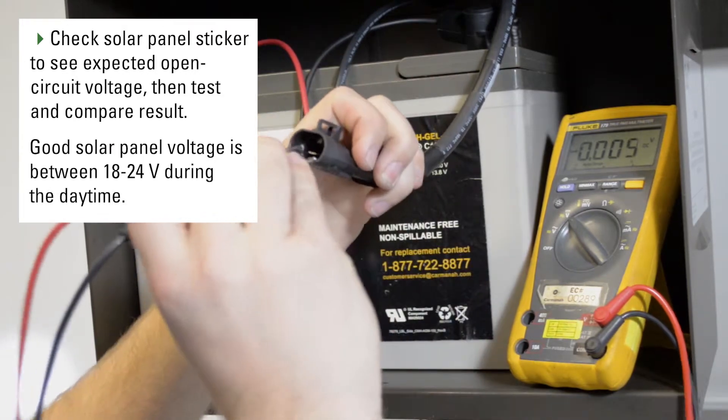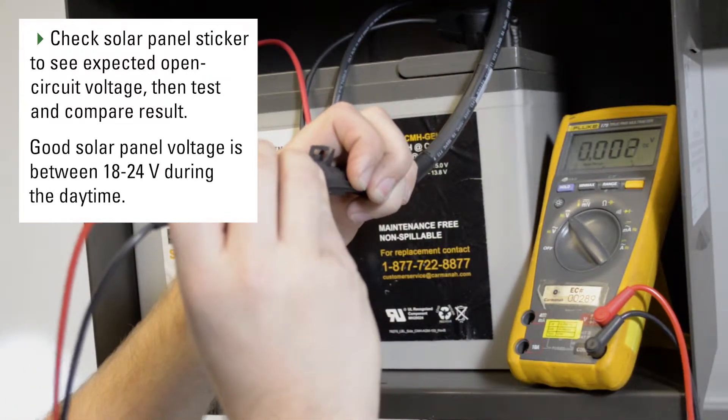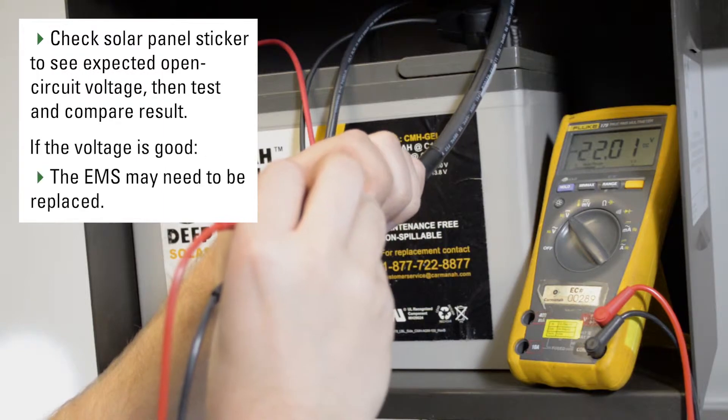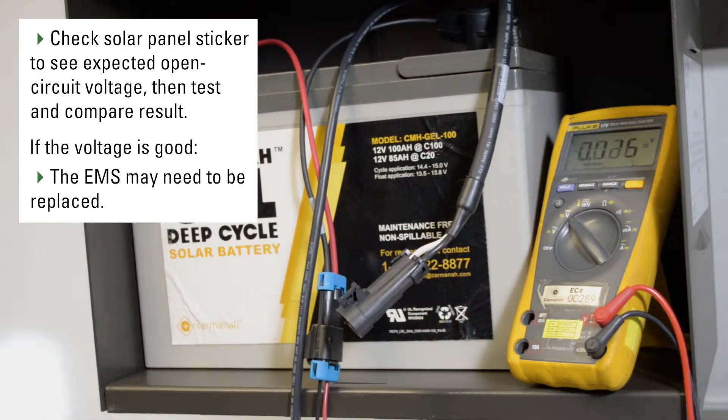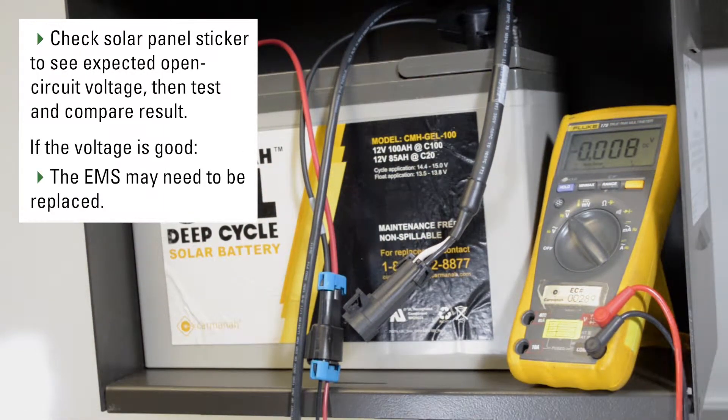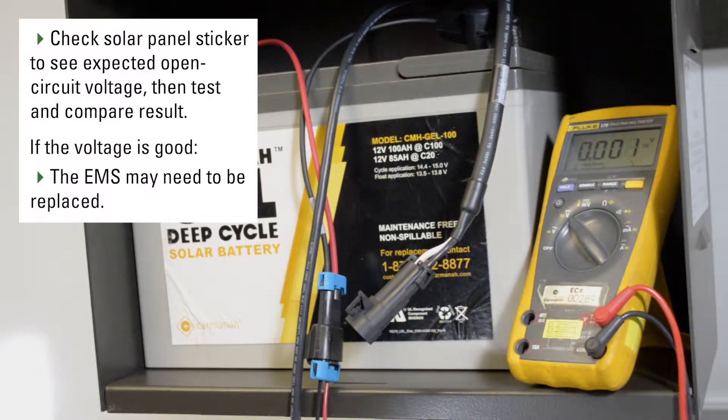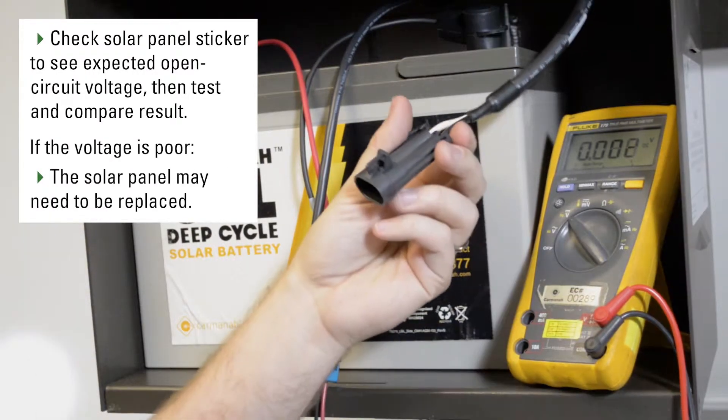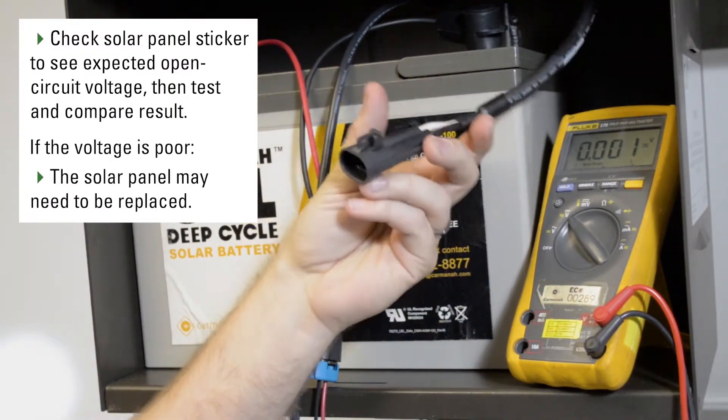When you test the open circuit voltage, you should expect to get a very similar number to that value. If you have a good open circuit voltage coming from the panel, it is possible that the EMS needs to be replaced as it is not functioning properly. If you don't get a good voltage coming from the panel, it may need to be replaced.